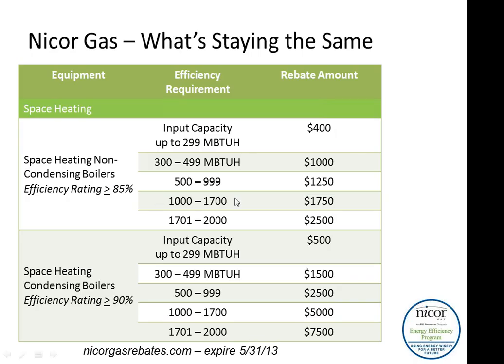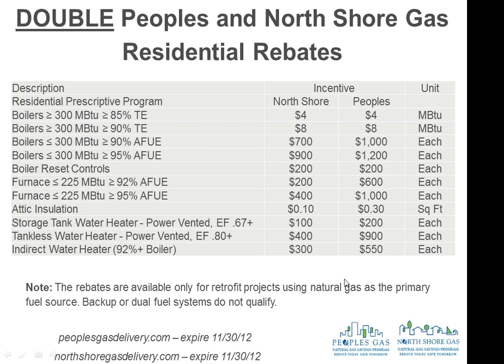If it's commercial Nicor, the dollar amounts are a little bit larger. If you get, say, a 500,000 BTU boiler like a ModCon 500 that we use here frequently, the rebate for that example would be, down here at the bottom, $2,500 for a 90% or more efficient boiler. If you're in the Peoples and North Shore gas territory, you should be aware that as of Friday, they just doubled their rebates. That rebate doubling goes from Friday of last week through the end of November. So basically from now to Thanksgiving, you can get double rebates, and this doubling is for both residential and commercial, by the way. For a traditional residential boiler, it can be 90 or 95% condensing boiler. For Peoples Gas in the city of Chicago, you get $1,000 or $1,200 for the 95%. For North Shore Gas, you get $700 or $900.